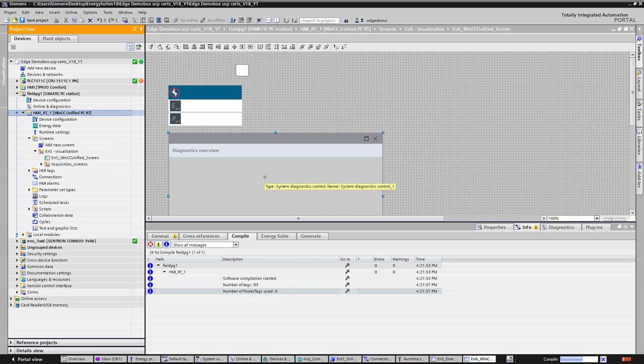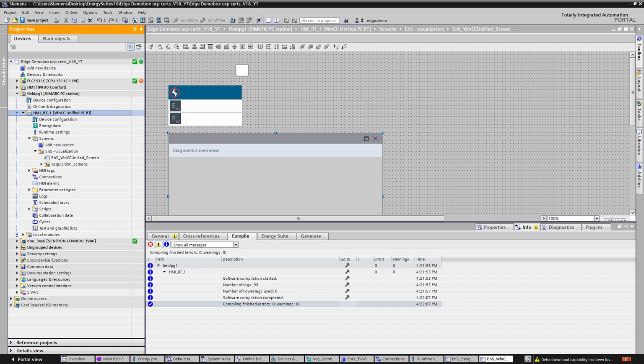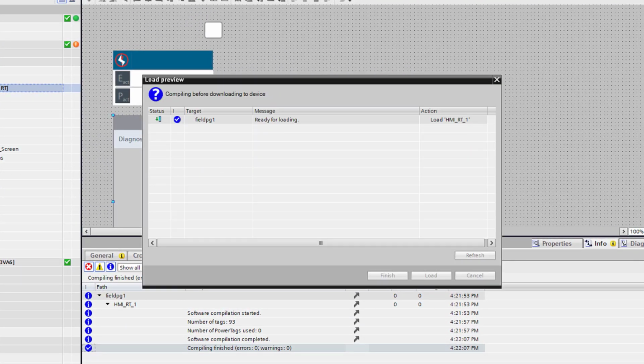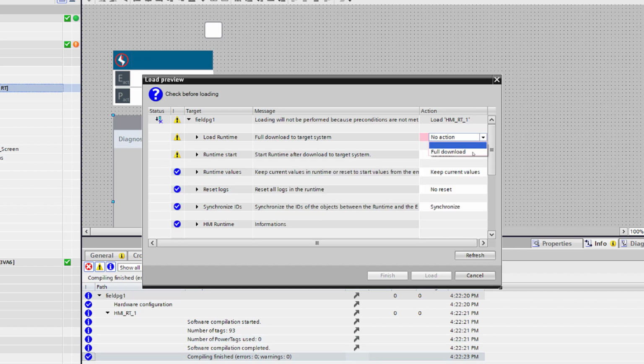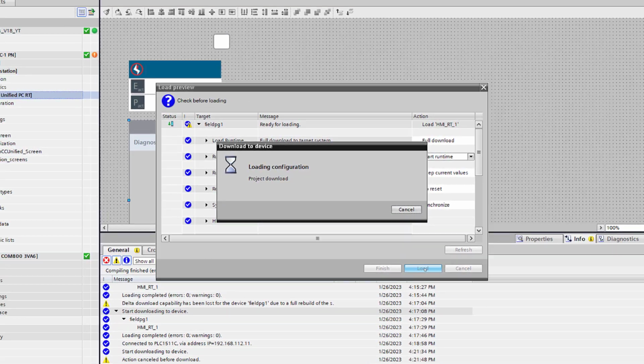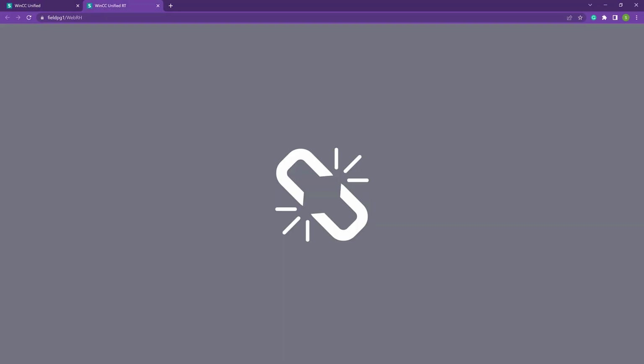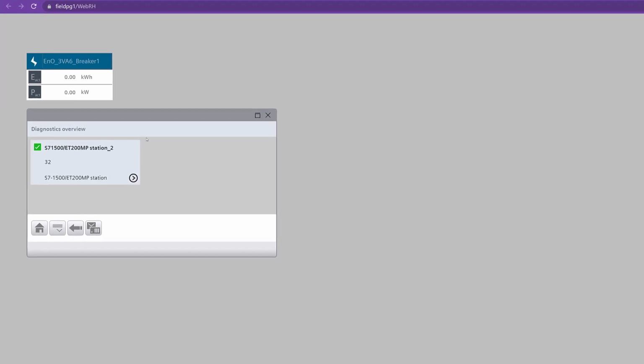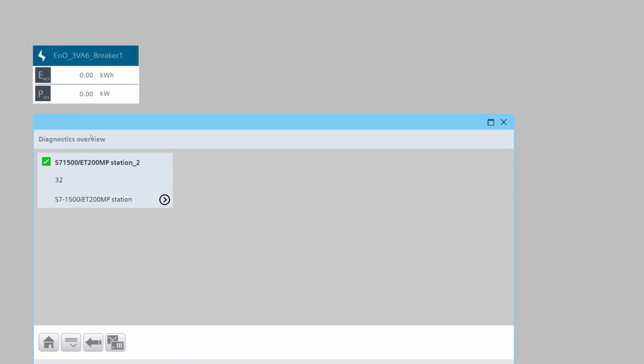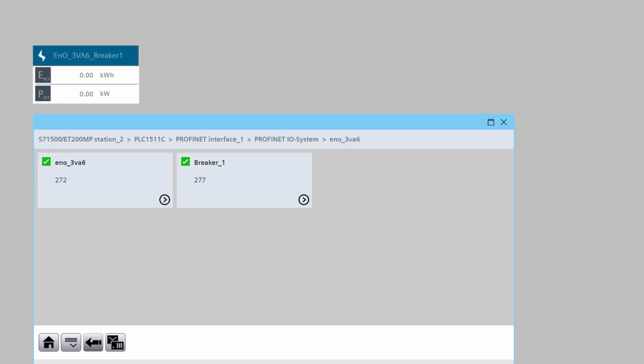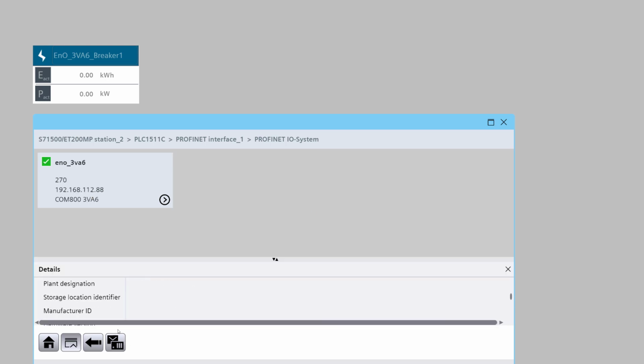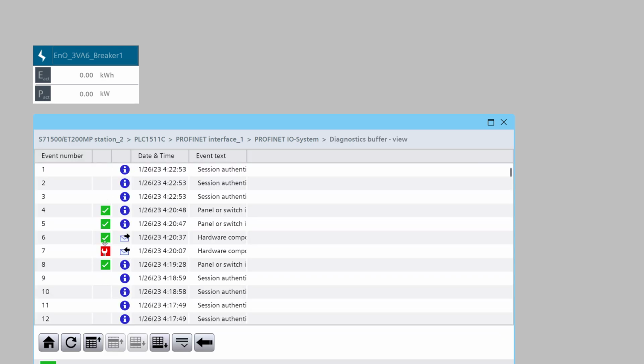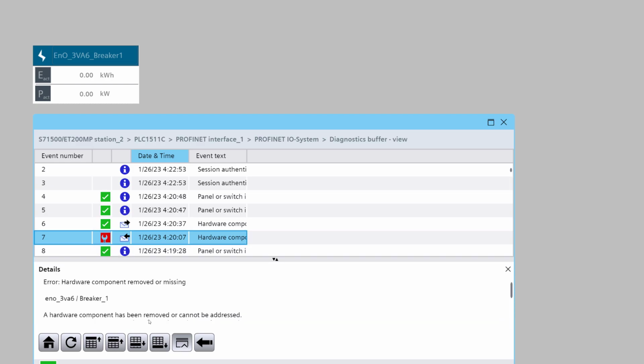Once we get it situated, we'll compile. And then go ahead and load to the field PG. Get the runtime running with the new changes. Here's the updated changes. What you can see here in the diagnostics overview is a simplified block format of our devices. So for example, if we expand the Profinet I/O system, you can see the 3VA6 COM800 along with the breaker one. Another advantage here is that you can see the PLC's diagnostics buffer, along with seeing details about each diagnostics entry.